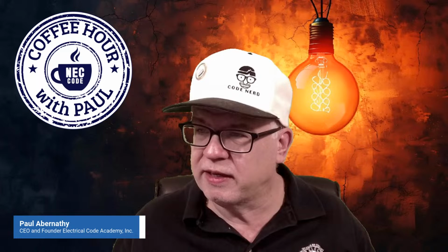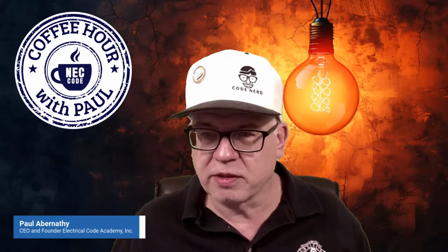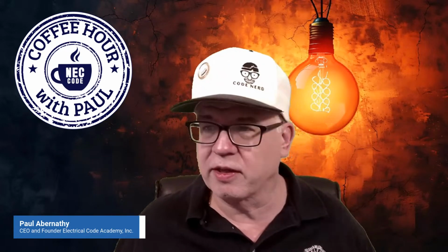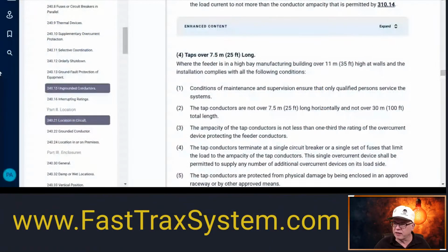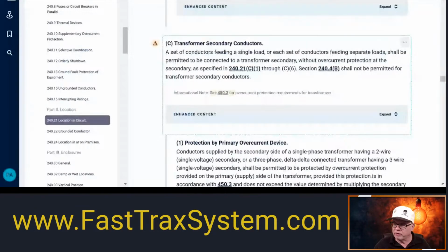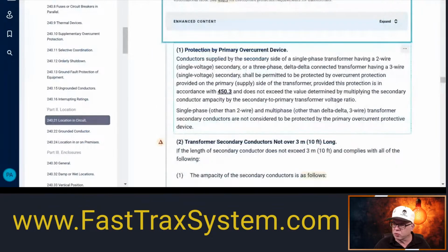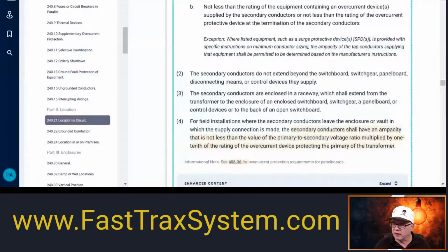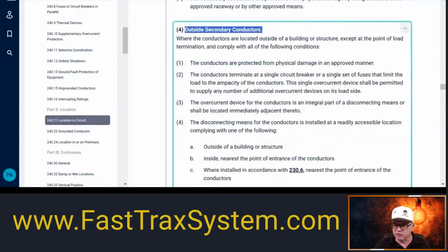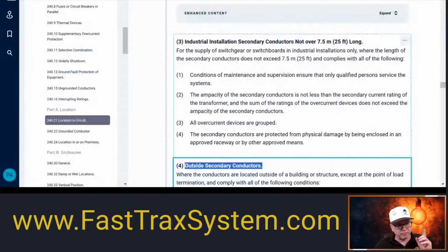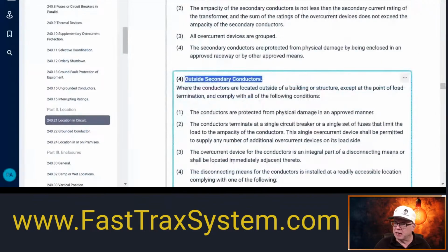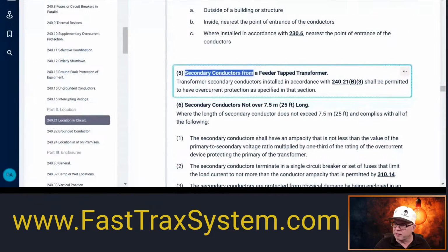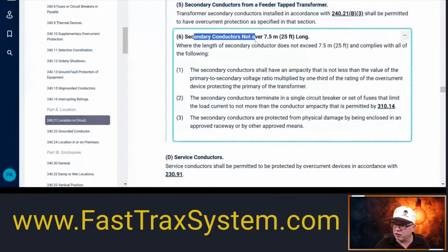But when you come to the feeders, we do have one here that talks about, I realized I wasn't sharing my screen with you. Hold on here. So as you can see, as I was talking about a second ago, for secondary conductors of transformers we have the not over 10-foot rule, the not over 25-foot rule, and outdoor secondary conductors, which are very similar to what we just talked about for the feeder outdoor. We have secondary conductors from a feeder tap.